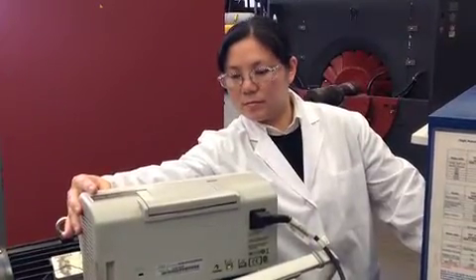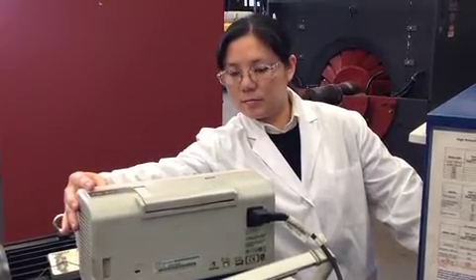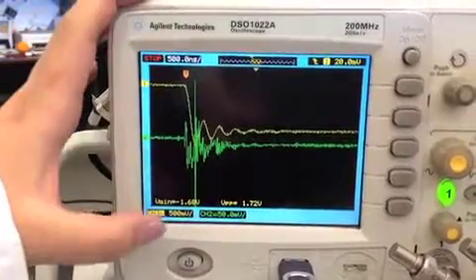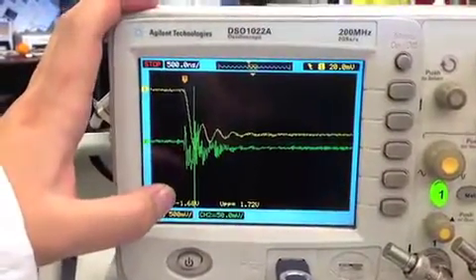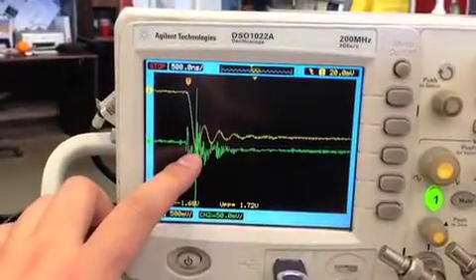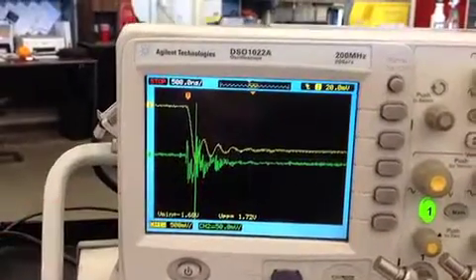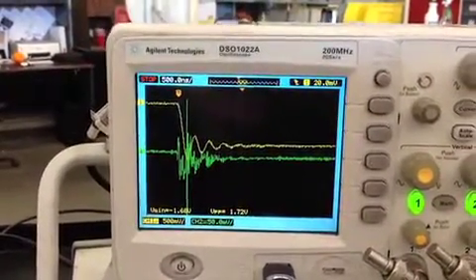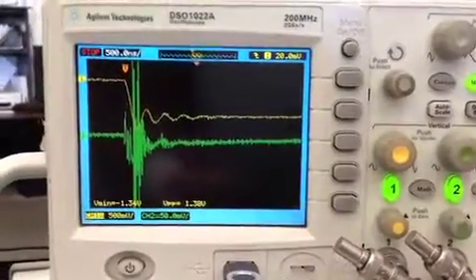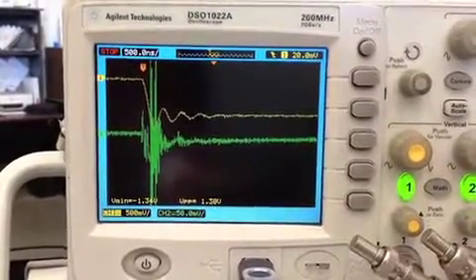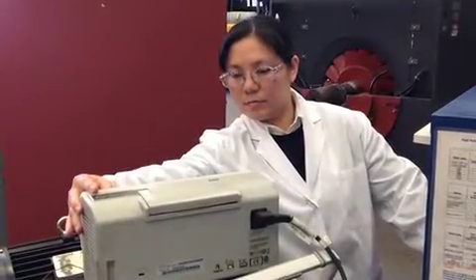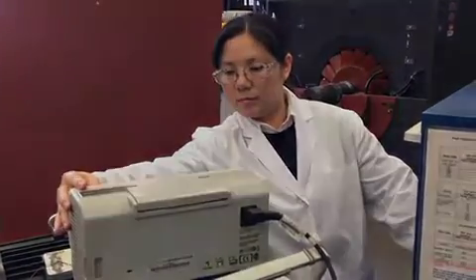So the test is stopped and we now check the voltage. This is a typical partial discharge response. We capture it in the green signal and it's happening at the lowest point of the yellow signal which tells you the level of the surge pulsing signals. This is in the lower left corner, reading a voltage, and that number times 2,000 was the voltage being applied when partial discharge was beginning.